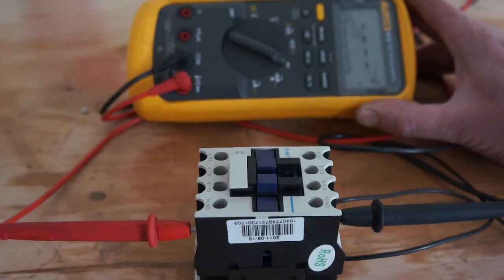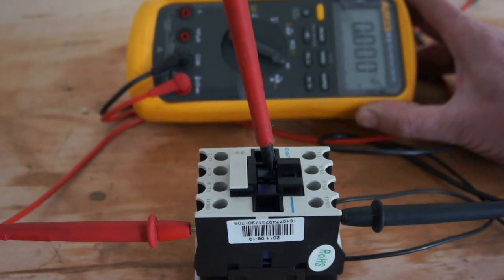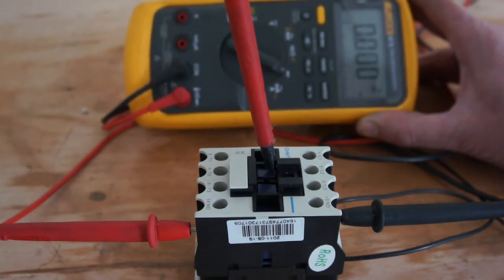Let's try it on the voltage drop. See that's 0.000. So you don't even pick up an ohm resistance doing the diode test. So at least that contact is working alright.